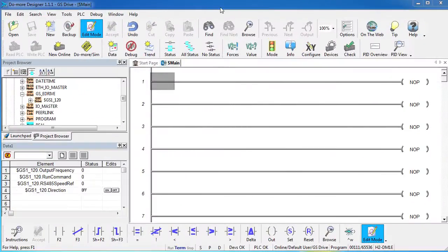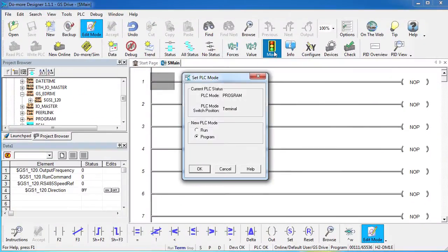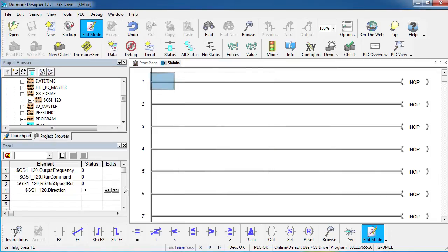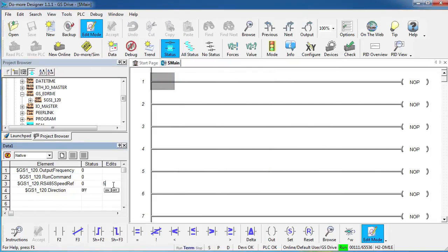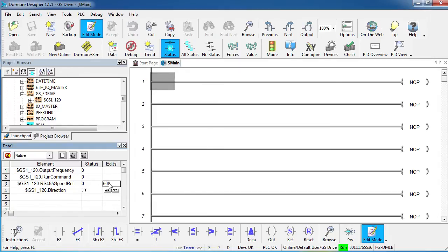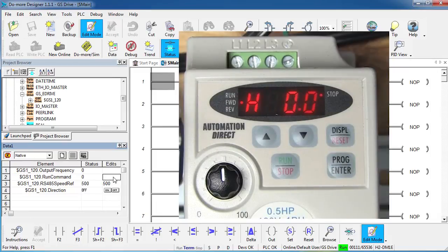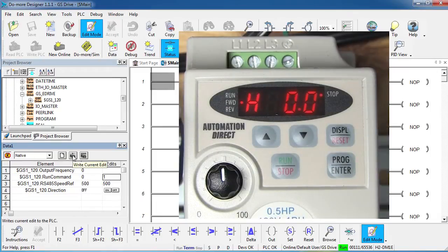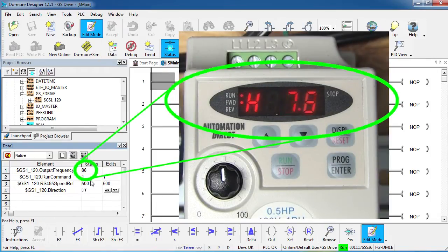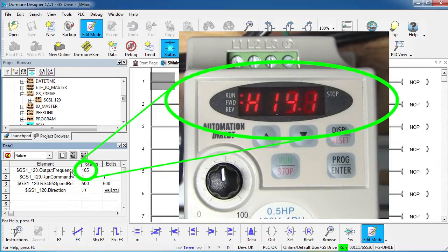Well, let's try it, let's go ahead and put the PLC in run mode, I'm going to set my new speed to 50 Hz, there's an implied decimal so I have to put 500 in there and I want the drive to start running. So I just put a 1 here and write it out. And sure enough, I see my output frequency slowly ramping up to 50 Hz.